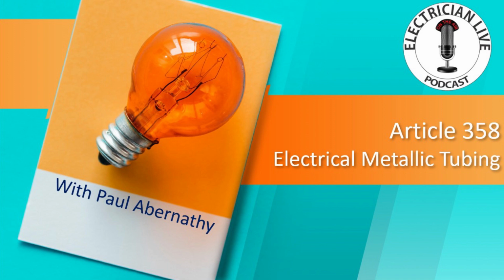If I put one cable in there, Chapter 9, Note 9 will tell me that I'm going to treat that as a single conductor. And then if it's only one cable in there, I don't want to exceed 53% fill. So it all works together, this beautiful thing that we have in Chapter 9, Table 1, but just understand all those notes, okay? But yes, unless the specific article on a cable type prohibits putting it in EMT, you certainly can put cables in EMT, okay?